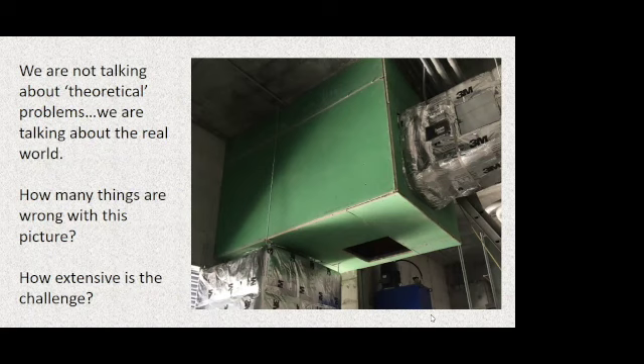We don't see bands on the plenum box, which is really strange because we see bands over there on the duct on the right, yet it's the same fire resistance product using the same designs. Why would we have the bands on the smaller duct and not on the plenum box? So the only thing holding this fire rated assembly together is aluminum adhesive tape. This is a bad imitation, mere wrapping paper. This is made to look fire rated, and is very dangerous because of that, because this is not even close to the technical manual for this product.